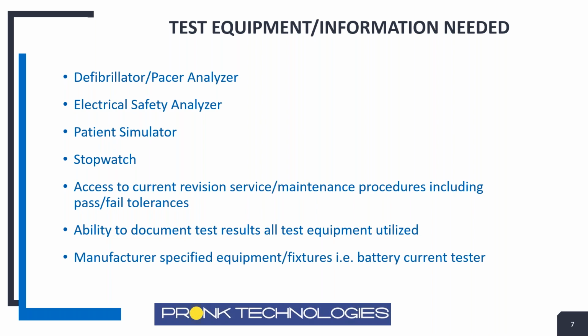There are some manufacturer-specific fixtures and test equipment that they require that are brand specific. So you'll see them in the service manual. Not all brands have the same fixturing. Some are specific to brands. One particular brand wants you to utilize a kind of proprietary battery current tester to test the battery charging circuit. And so you'll have to make sure you look at these service manuals for some of these details on specific fixturing you also need to have on hand when doing the service.